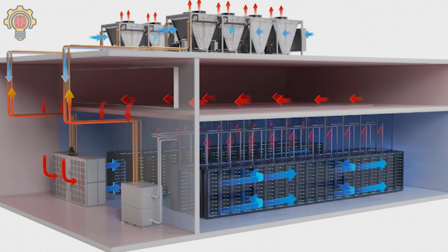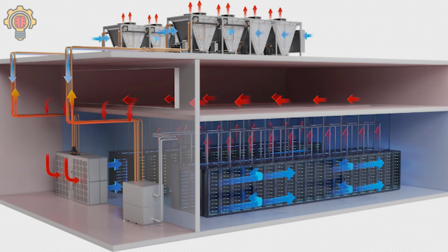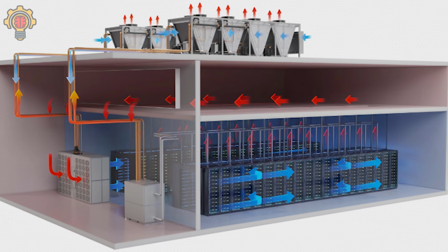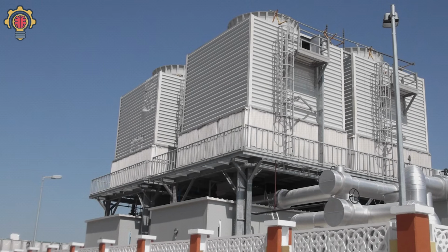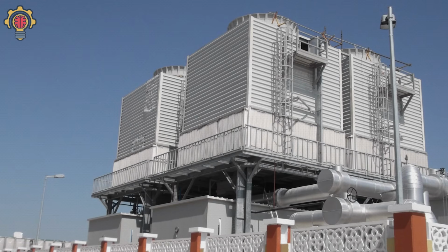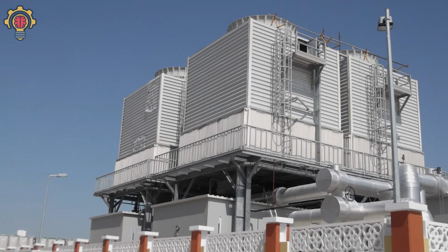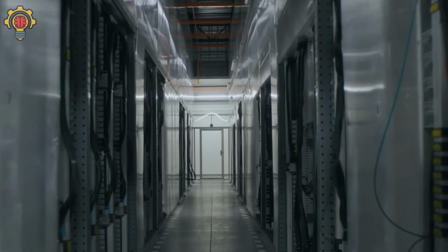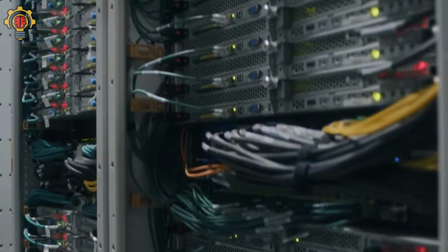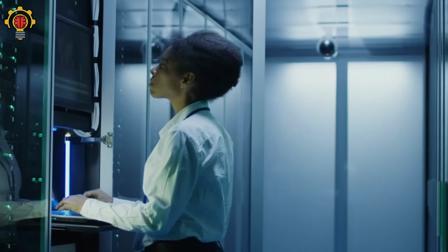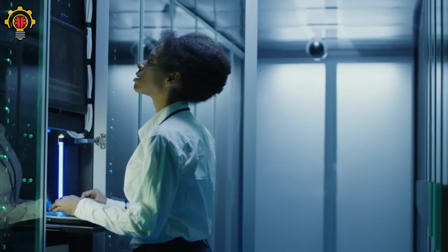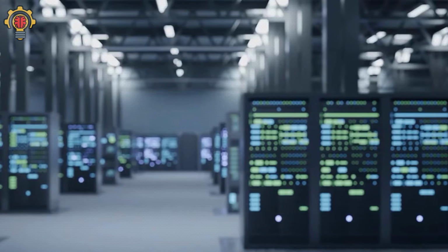Traditional room cooling systems started struggling to keep up, and this forced engineers to rethink airflow completely. That is when the concept of hot aisles and cold aisles became one of the most important designs in modern data centers. Here's how it works. The front of every server rack faces the cold aisle. That side receives cold supply air directly from the cooling system. The servers pull in that cold air, absorb heat internally, then push the hot exhaust air out the back of the rack into the hot aisle. Simple idea, but incredibly effective.